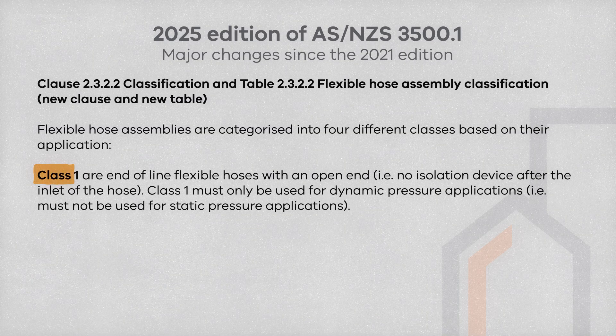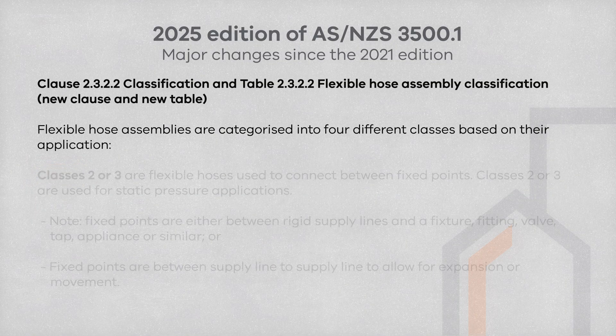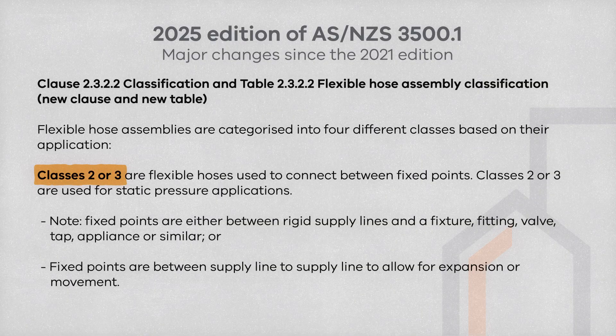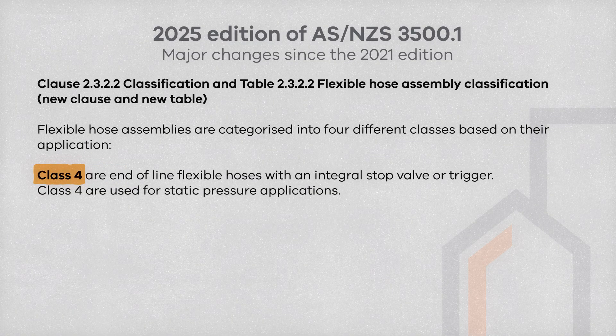For Class 1, these are end-of-line flexible hoses with open ends, having no isolation devices after the inlet of the hose. Class 1 must only be used for dynamic pressure applications, not static pressure applications. For Class 2 or 3, flexible hoses are only to be used to connect between two fixed points — such as between a pipe and fixture, fitting, valve or tap — and are used for static pressure. For Class 4, they are end-of-line flexible hoses with an integral stop valve or the like, and are used for static pressure applications.